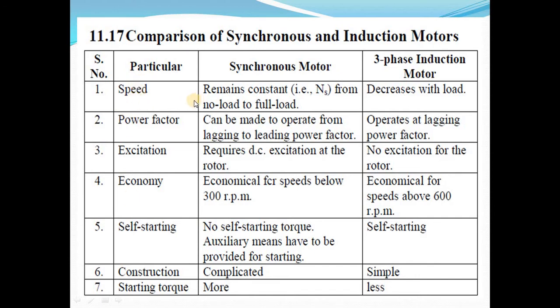The first point of comparison is speed. In a synchronous motor, the speed remains constant from no load to full load. In the three-phase induction motor, if the load is increased, the speed decreases with load. So the synchronous motor speed is constant from no load to full load, whereas the induction motor speed decreases with increasing load.